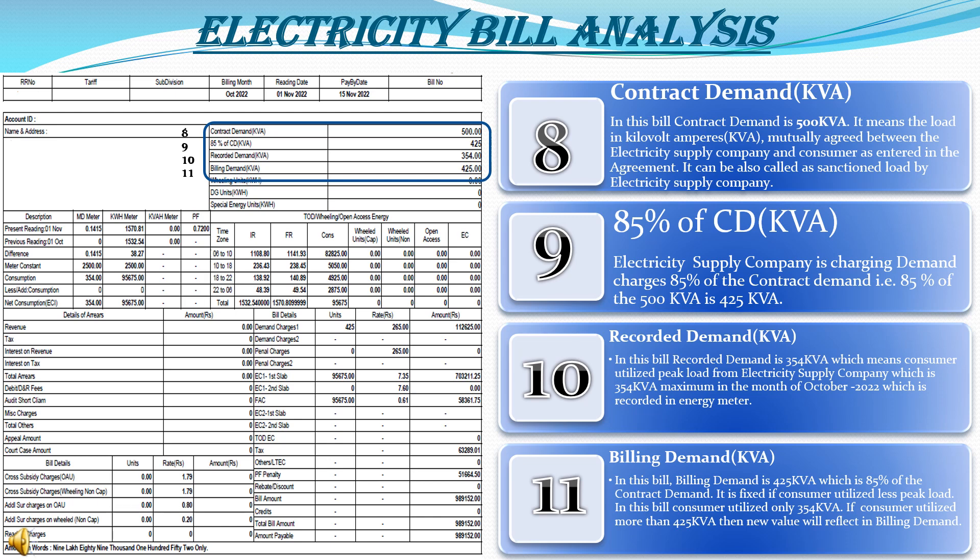The billing demand in this bill is 425 KVA, which is 85% of the contract demand — that is 500 KVA. If the consumer uses up to 425 KVA, it will reflect as 425 KVA only. If the consumer utilizes more than 425 KVA, the new value will reflect in the billing demand, and extra demand charges will be added on the billing side.